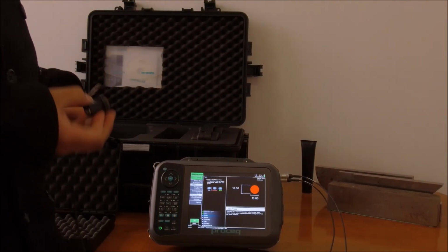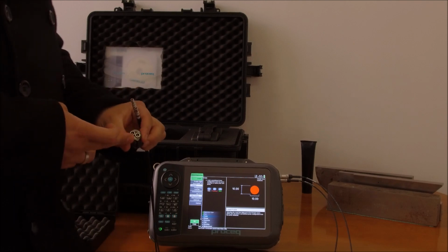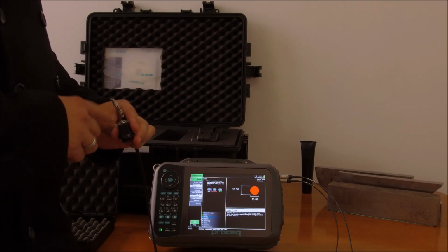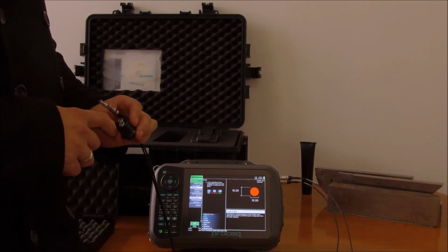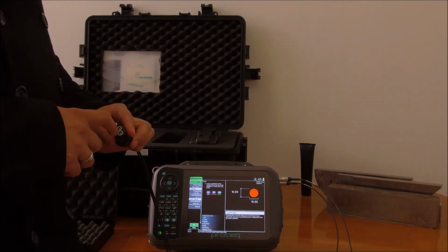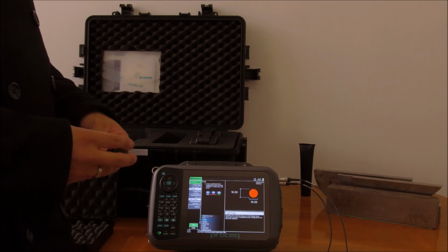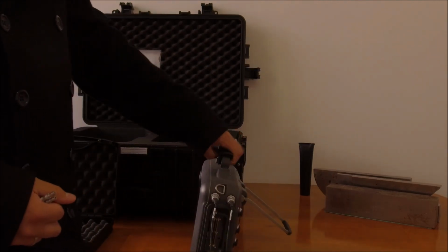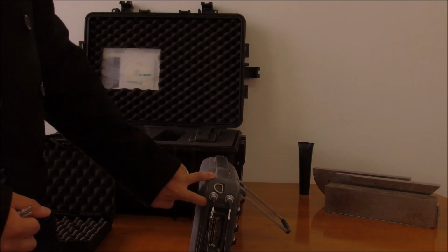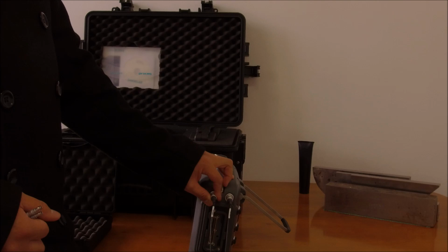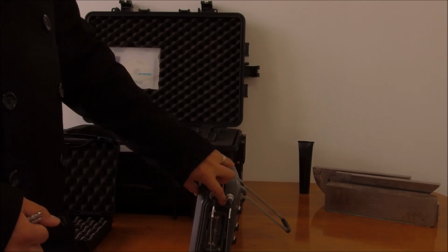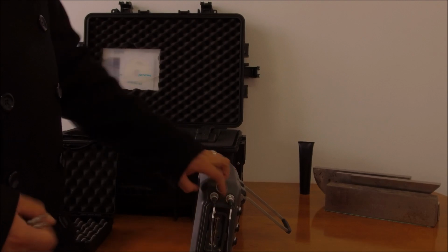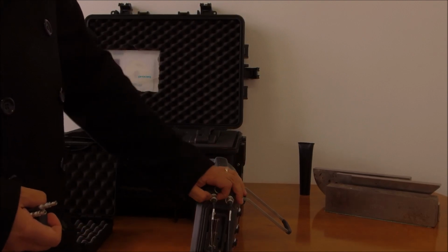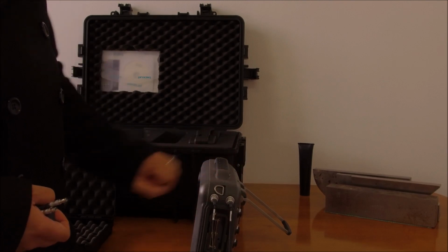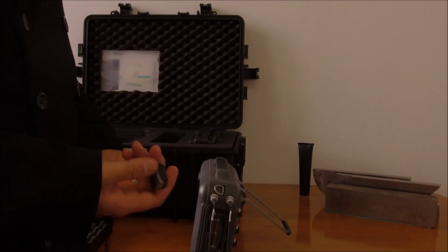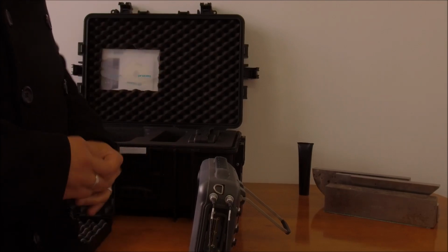So we're just going to connect up this probe. As with any probe, you want to have a look up the top and see if there's any indicator as to which one is the transmit and which one is the receive. Normally you're looking at either a T or a red dot or something like that. Okay, and then if you did get an indication of that, you would have a look at the side here, and you would see that one side says transmit/receive. So that's for any mono crystal or single crystal. And then you see one side has receive. So if you did have one that indicated to you which one was transmitting, you would connect it to this one here that says T/R. Okay. In this instance, this probe doesn't differentiate between either side, so it doesn't matter too much.